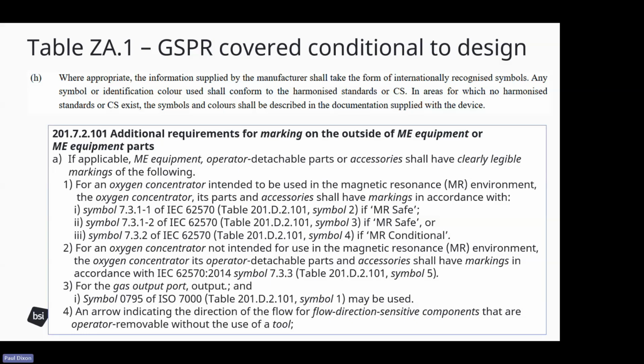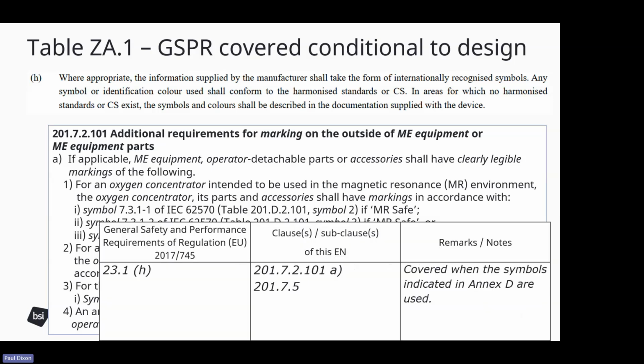If you read this carefully, you can see that although A1 does say shall have markings in accordance with, A3 simply says may be used. And so when this went to assessment, the HAS assessment agreed that this 23.1 was covered in part by 201.7.2.101A, but they insisted on a remark that it's only covered when the symbols that are indicated in Annex D are actually used by the manufacturer. So this is another example of a remark in the Annex Z that does need to be considered by the manufacturer when they're determining whether or not they can claim this clause.